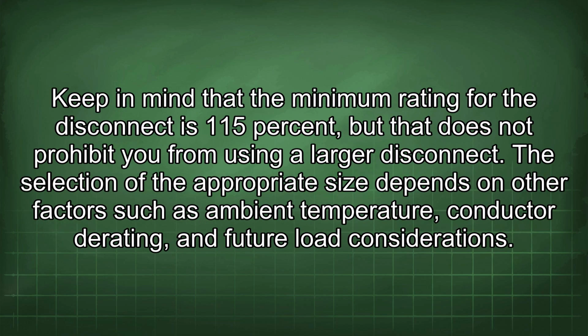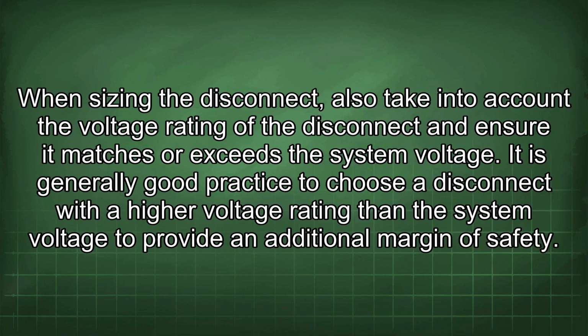Keep in mind that the minimum rating for the disconnect is 115%, but that does not prohibit you from using a larger disconnect. The selection of the appropriate size depends on other factors such as ambient temperature, conductor derating, and future load considerations. When sizing the disconnect, also take into account the voltage rating of the disconnect and ensure it matches or exceeds the system voltage. It is generally good practice to choose a disconnect with a higher voltage rating than the system voltage to provide an additional margin of safety.